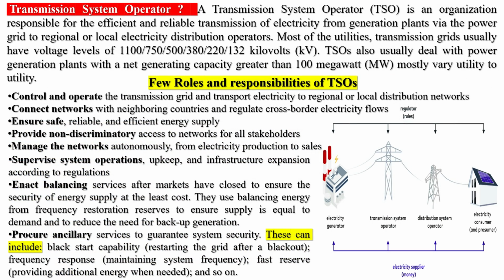Transmission system operator. A transmission system operator is an organization responsible for the efficient and reliable transmission of electricity from generation plants via the power grid to regional or local electricity distribution operators. Most of the utilities' transmission grids usually have voltage levels of 1,100, 750, 500, 400 or 380, 230 or 220, or 132 kV. TSOs also usually deal with power generation plants with a net generating capacity greater than 100 megawatt. Mostly vary utility to utility.